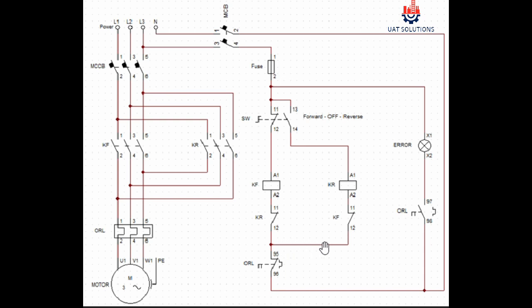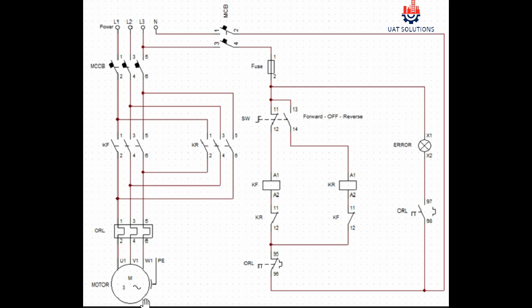While neutral will pass through point 95 of overload to the point 12 and 11 of contactor KF, which is connected to coil terminal A2 of contactor KR, resulting in energizing the contactor KR to allow the motor to run in reverse direction.